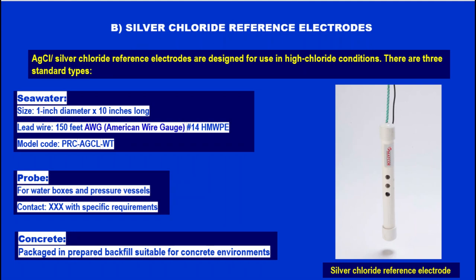The next type of electrode is Silver/Silver Chloride Reference Electrodes, designed for use in high chloride conditions. There are three standard types: 1. Sea water applications — size 1-inch diameter, 10-inch long, with a probe lead wire of 150 feet, 14 AWG, high molecular weight polyethylene. Model code: PRCAGCLWT. 2. Probe for water boxes and pressure vessels — contact the supplier with specific requirements. 3. Concrete — packaged in prepared backfill suitable for concrete environments.